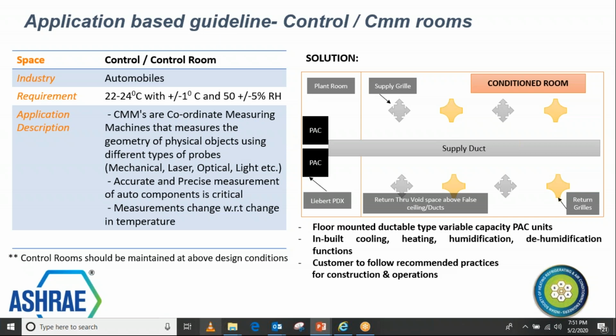So a ductable system would be preferred, but at the same time, to have more power savings, it is good to have variable capacity control on the compressors, like a digital scroll kind of thing, or an inverter compressor kind of thing, because that will ensure that your power consumption at part load is lower. We know that the systems do not operate all around the year, and also the ambient air is not always at peak. So with this impact put together, the load inside the room, which is designed for a certain capacity, is always not 100%. With occupancy and the load not being stagnant, the load inside the room becomes variable. So it's very important that the cooling system can go for variable capacity. Although the initial cost may be a little higher, the overall operational cost is always lower.